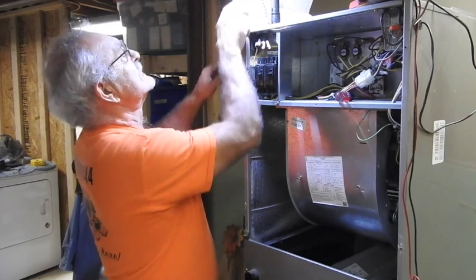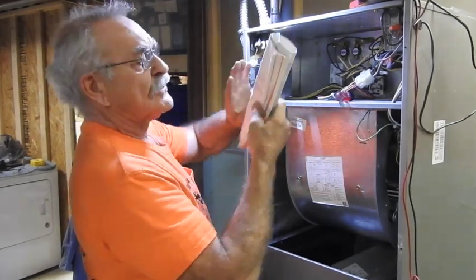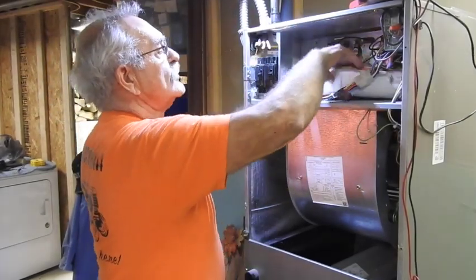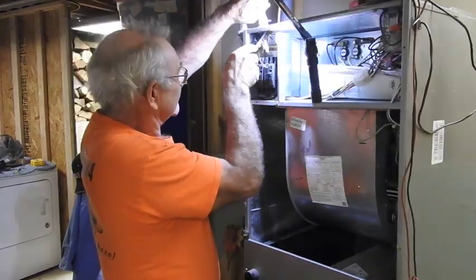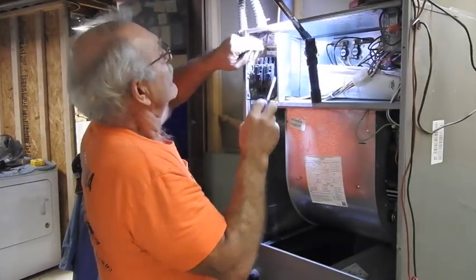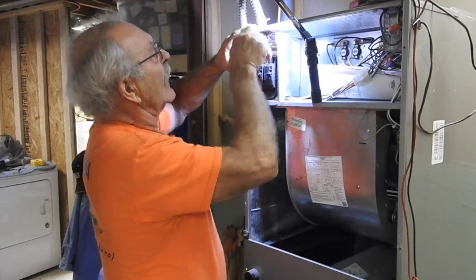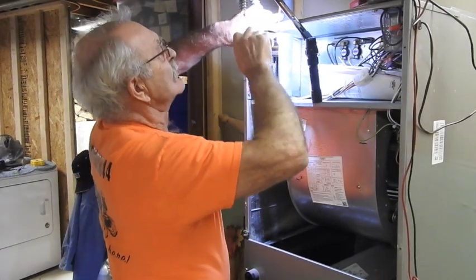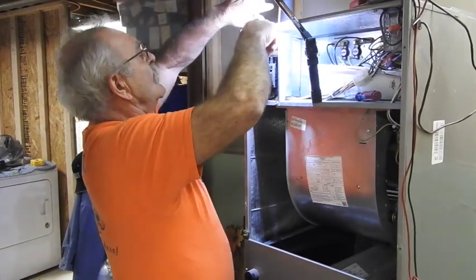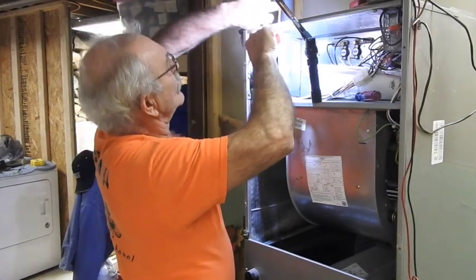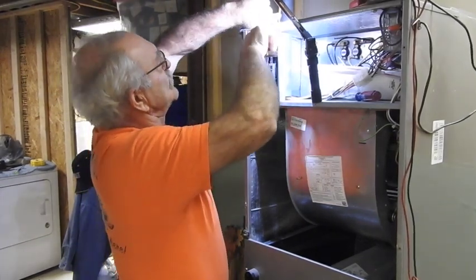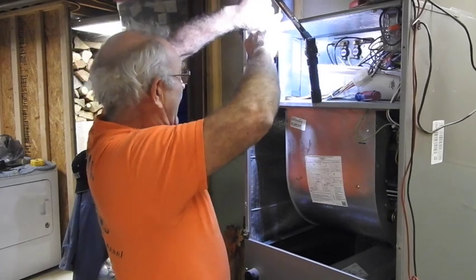Okay, I've got to get these nuts and stuff loose in here. This is original instructions, so we'll make sure those stay with the furnace. Oh, guess what? There's a second ground off of the second circuit. It's actually grounded to the ground lug over here. You know you're going to be reusing this stuff on the new furnace, so make sure you don't chafe or scratch the wires too badly.